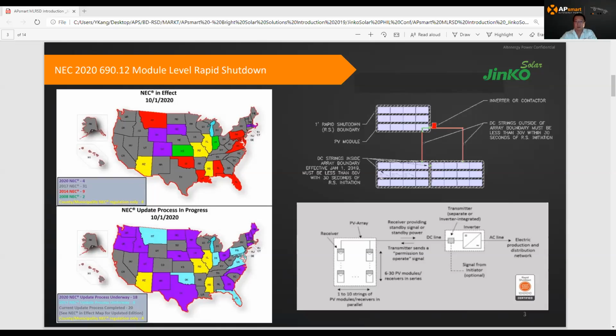During 2017, they updated their requirement from 690.12 to get into the array, which means inside the boundary, within 1 foot of the array from the module, the voltage needs to drop below 80 volts within 30 seconds after initiating the rapid shutdown device. You can see on the left side, this has already been adopted in over 33 states in the US, and there are more coming. So this standard is pretty much already adopted in the US market right now.